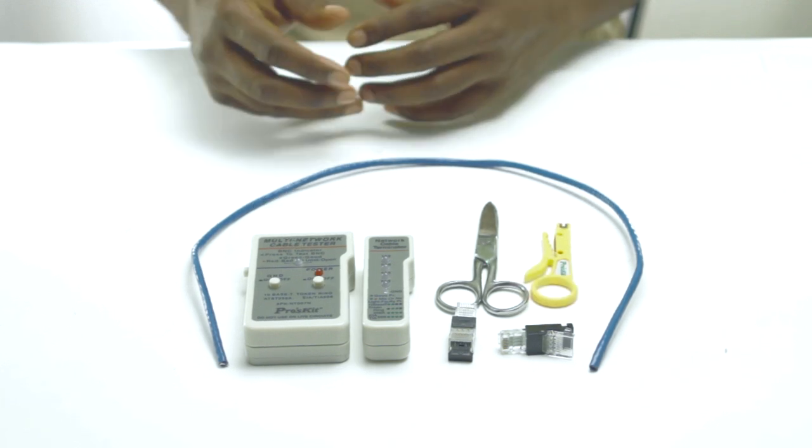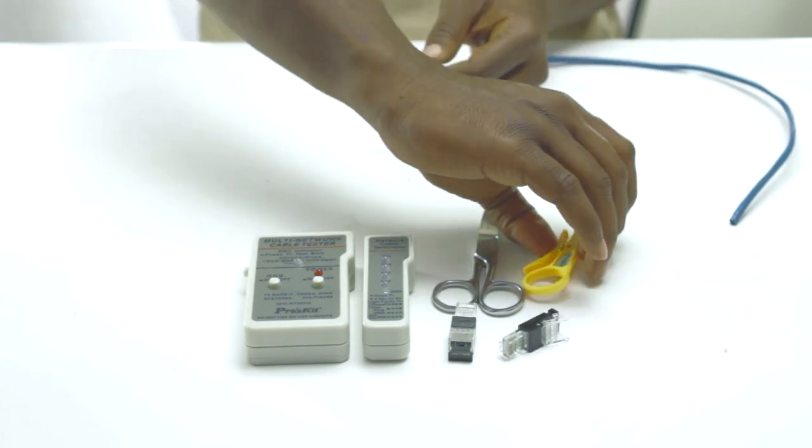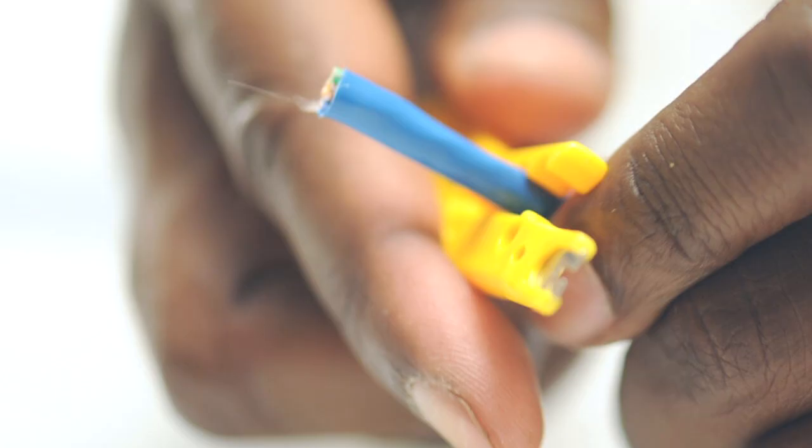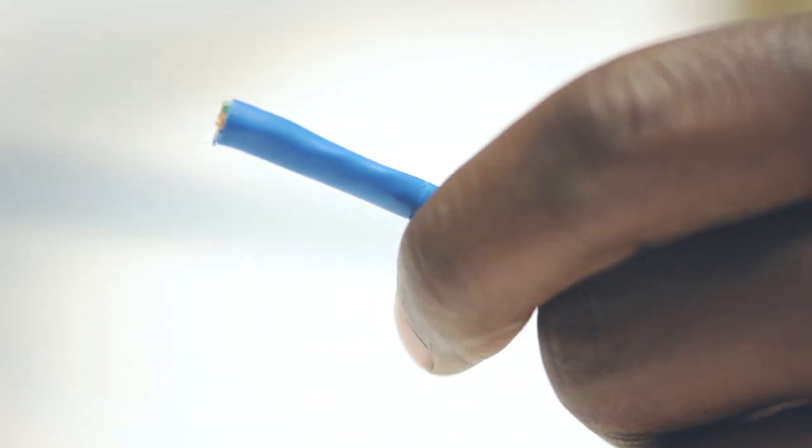The first step is to take your strip tool and remove the jacket. Here we are using a rotary stripper that rotates around the outside of the cable and slices the cable with a razor blade.